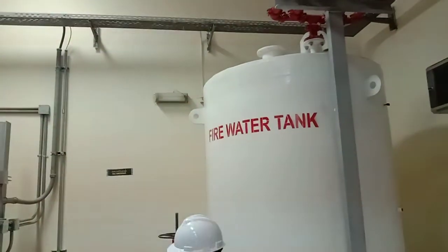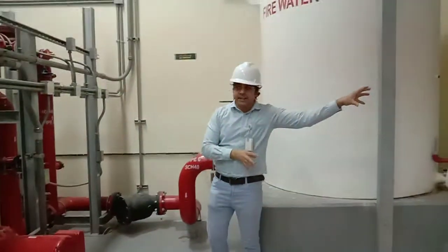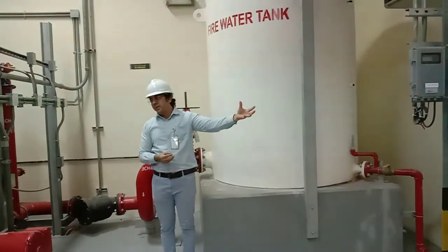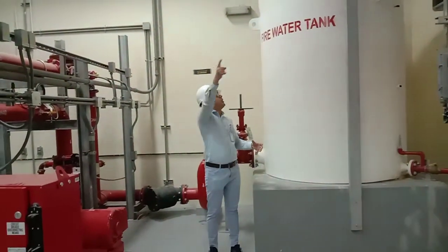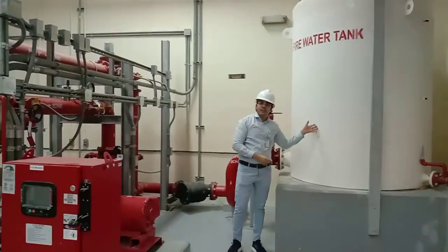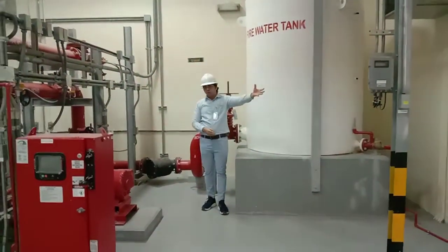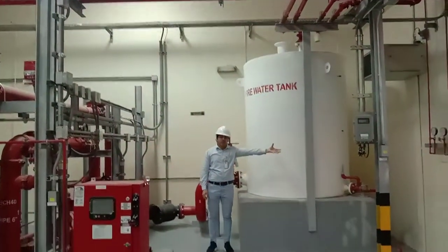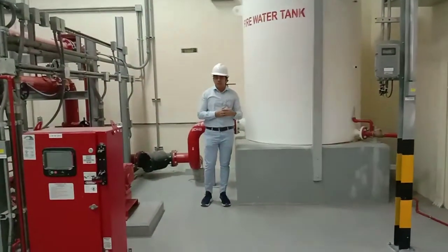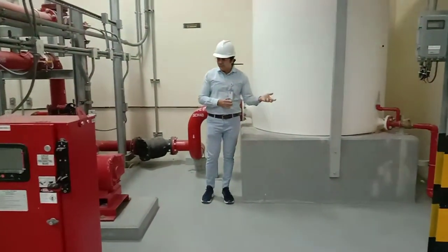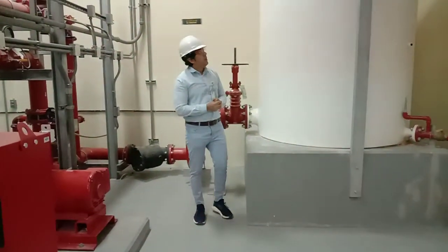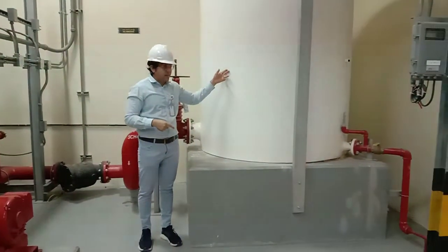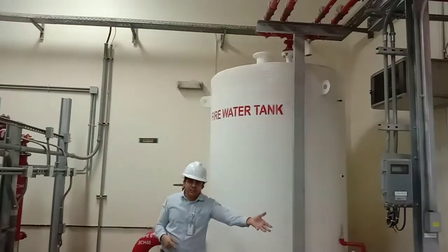So the beauty of this flow meter is that it is better than the one I discussed in the beginning. We don't have to discharge water into the atmosphere. What we have to do is install a flow meter, and the discharge line will go back to the tank. Those lines will come directly to the tank, and we can also measure the flow and pressure and do the pump performance test. So this is better than the one I discussed in the beginning, to save water and avoid other kinds of problems while draining the water from the discharge. The discharge line from this arrangement can go to the tank, or you can take it anywhere outside at some location.